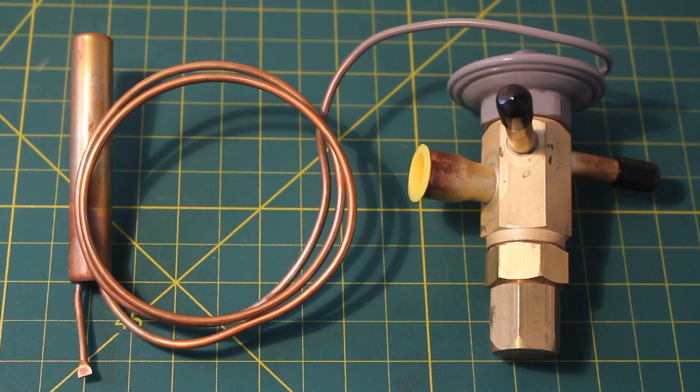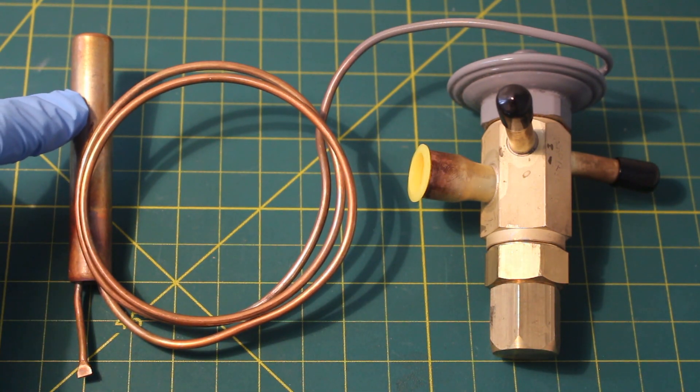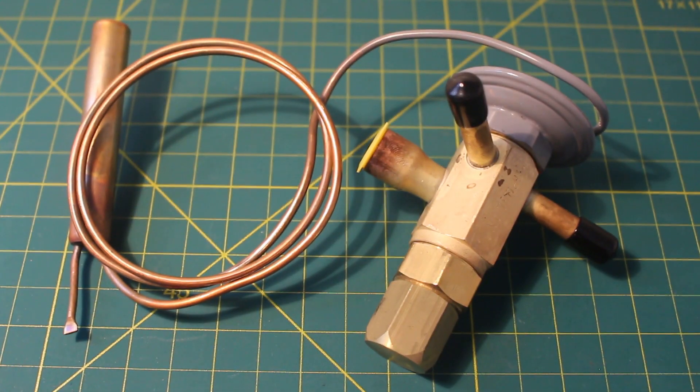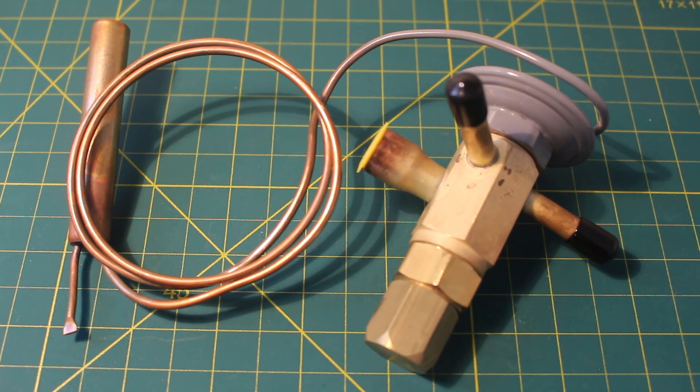This component is known as the thermal bulb, the sensing bulb, or the feeler bulb. Inside it is filled with the same gas that is in the system, or it could come with a cross charge of two refrigerants. This component gets strapped down tightly to the suction line where refrigerant is a low-temperature, low-pressure vapor. This is a type of expansion valve, and the expansion valve controls the flow and amount of refrigerant entering the evaporator.